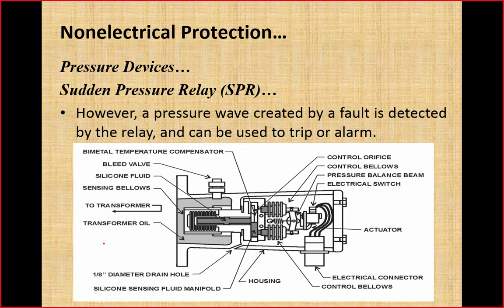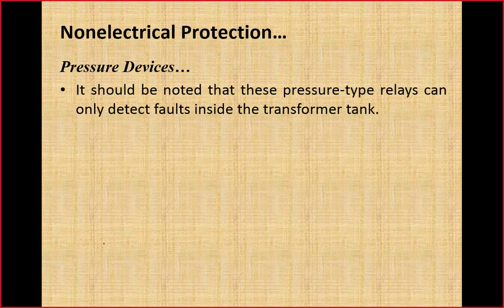So this is a more complicated working diagram of a SPR sudden pressure relay. It should be noted that these pressure type relays, whether it is Buchholz relay or SPR sudden pressure relay, can only detect faults that will occur within the transformer tank.